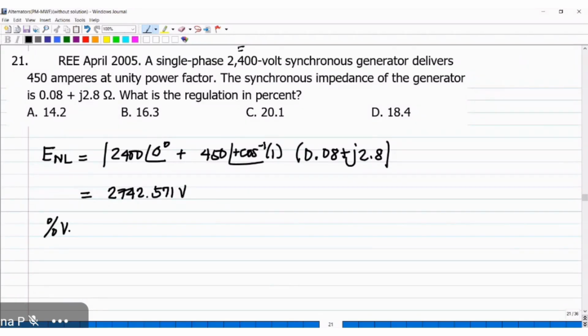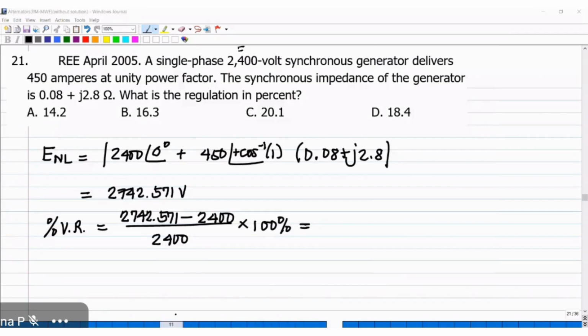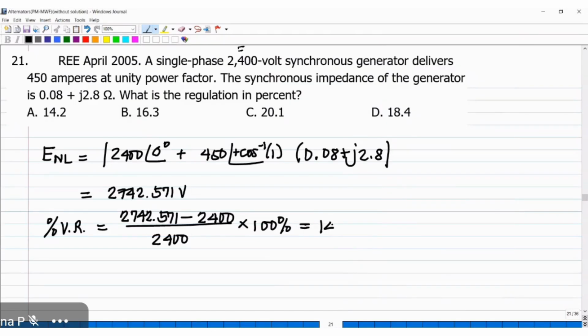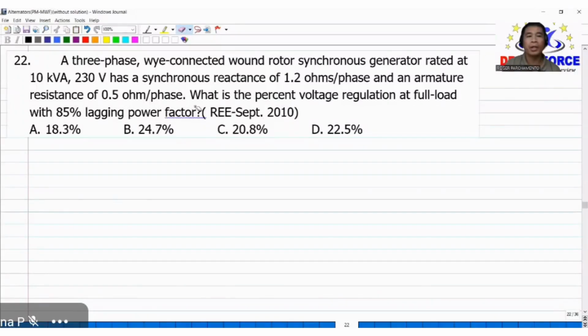volts. So therefore, the percent voltage regulation, since we are dealing with a generator, is the no load value of the voltage, 2742.571, minus the full load 2,400, over the full load voltage 2,400, multiplied by 100%, which is equivalent to 14.274%. That will be letter A. Next is the percent voltage regulation at full load with 85% lagging power factor.